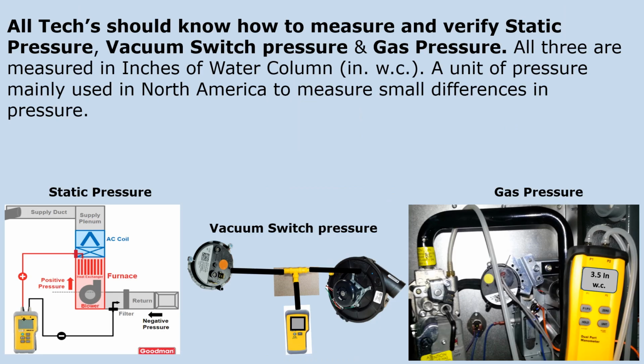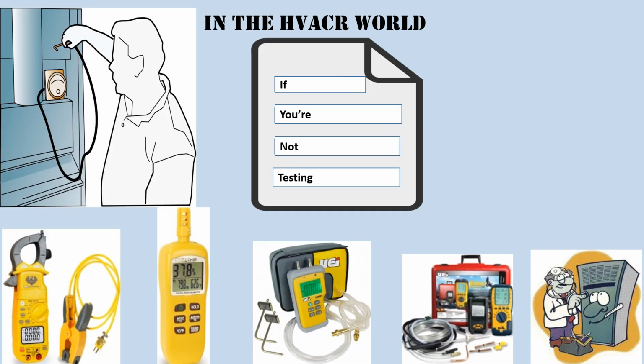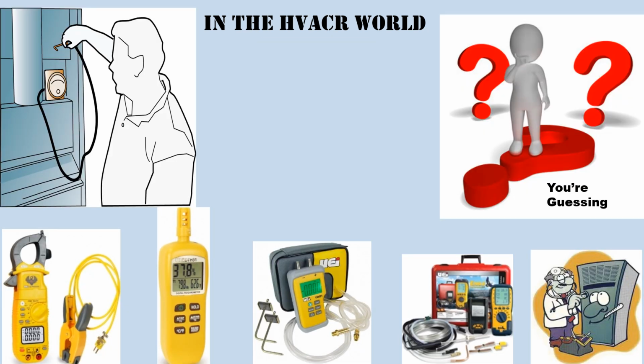All techs should know how to measure and verify static pressure, vacuum switch pressure, and gas pressure. All three are measured in inches of water column, a unit of pressure mainly used in North America to measure small differences in pressure. In the HVACR world, if you're not testing, you're guessing.